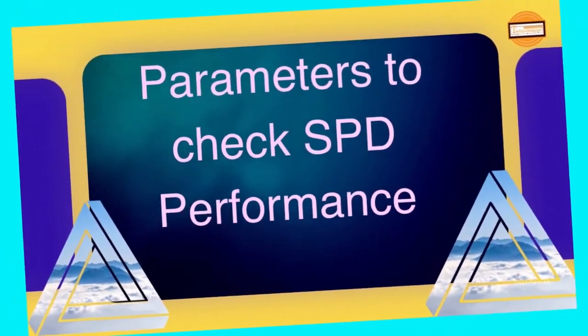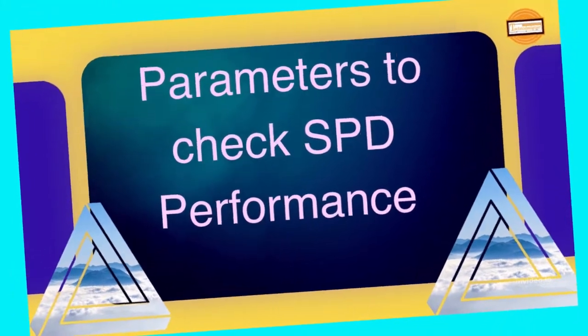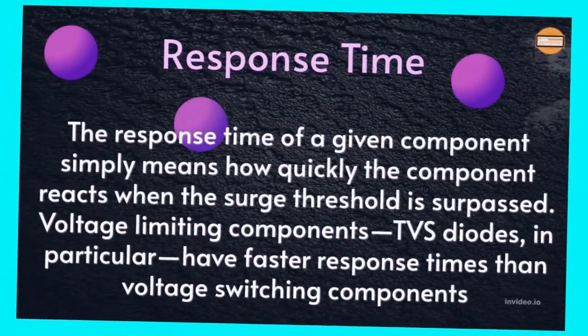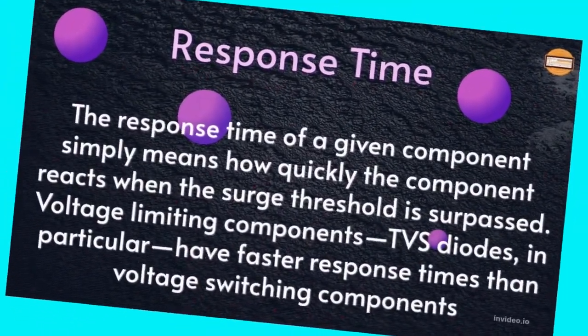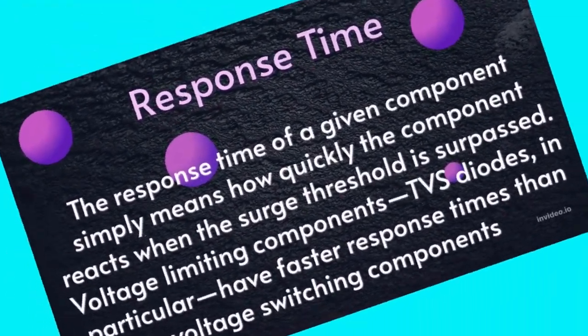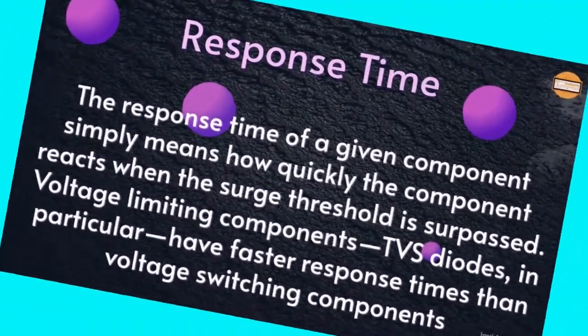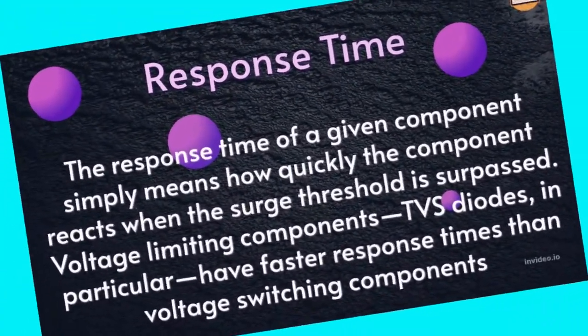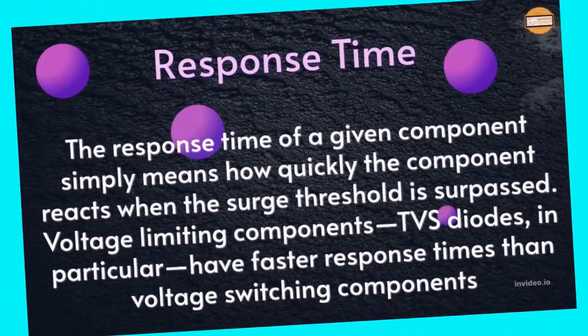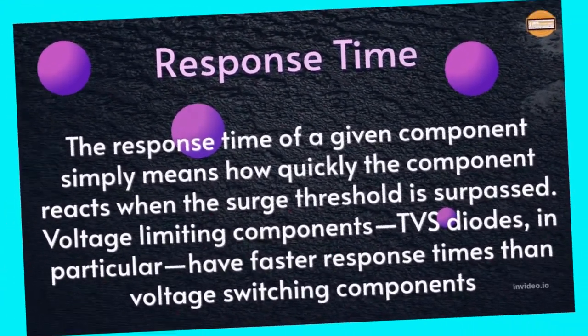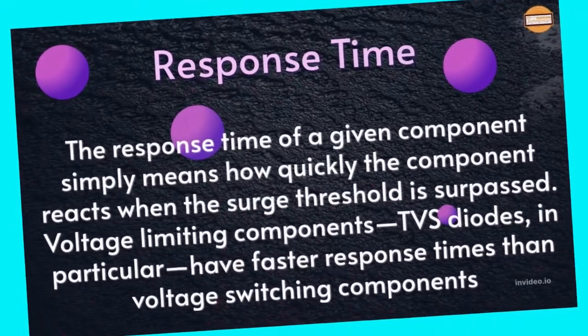Parameters to check SPD performance. Response time is how quickly a component reacts when the surge threshold is surpassed. Voltage limiting components, such as TVS diodes in particular, have faster response times than voltage switching components.